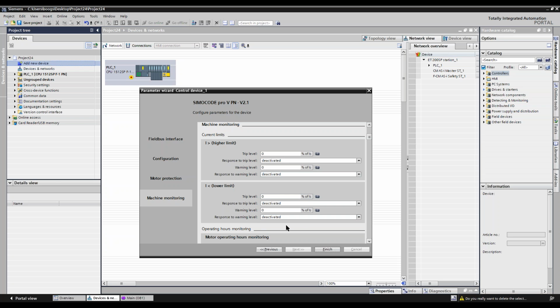I can do that in the SIMOCODE. I can set up those lows and highs and put that logic in the SIMOCODE as quickly as saying at this percentage of 85, or 84, sorry, and I can go to 72. Whoops, sorry, fat fingered it. And then I can set this: if it hits 84% of the full load amps, then I'm going to trip or signal. Or if I get to 70, I'm going to warn. So here's where I can go in and set that high and that low inside the SIMOCODE.